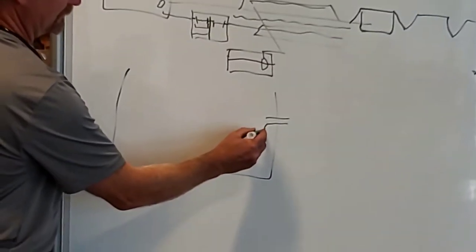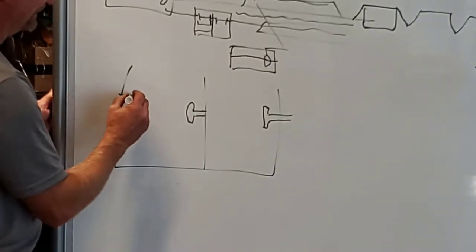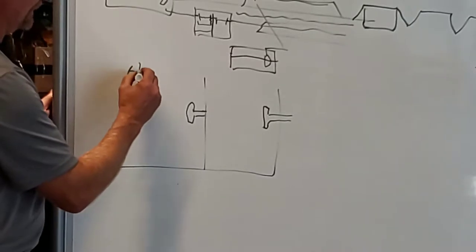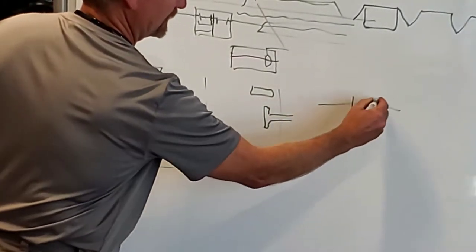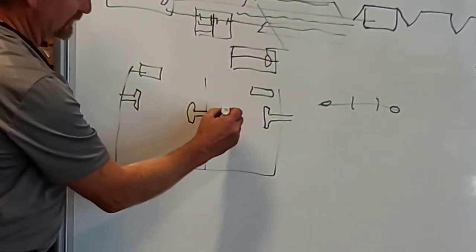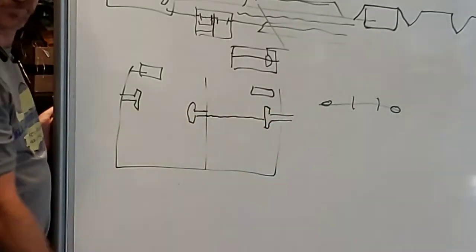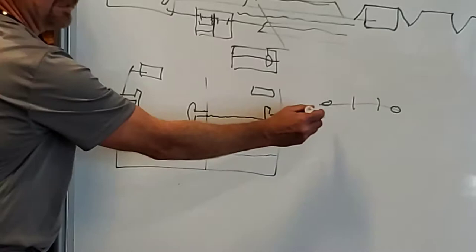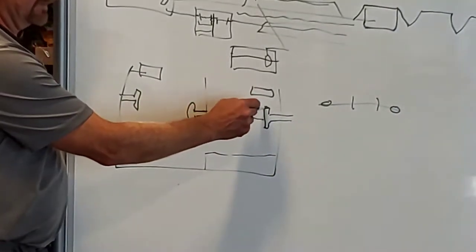The tee goes down from the top. The lid will have a 24-inch or 20-inch configuration, and sometimes six-inch lids that look down into the top of the baffle. I can see where the liquid level is — it should be right at the bottom of the outlet — and we slide the filter in so just the clear liquid works up through the filter and out of the tank. If the bottom of the tee got plugged for some reason, eventually it would fill and spill over the top and go into the next tank. That's why you wouldn't use an elbow — if it plugs at the bottom you can't see it.